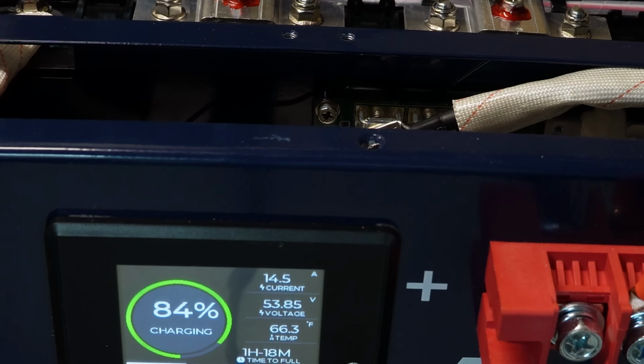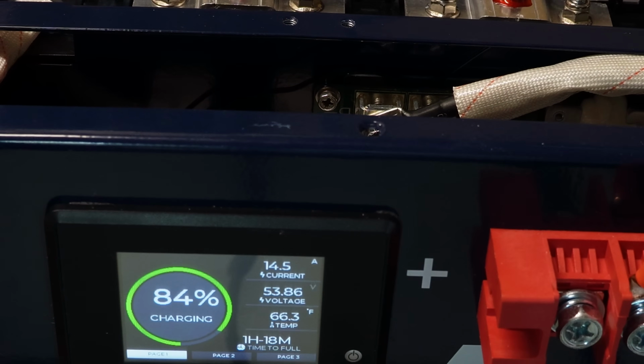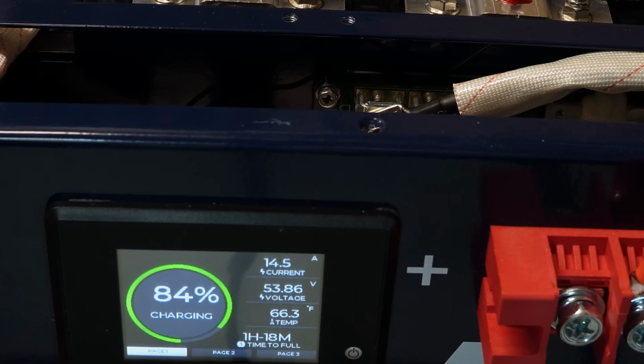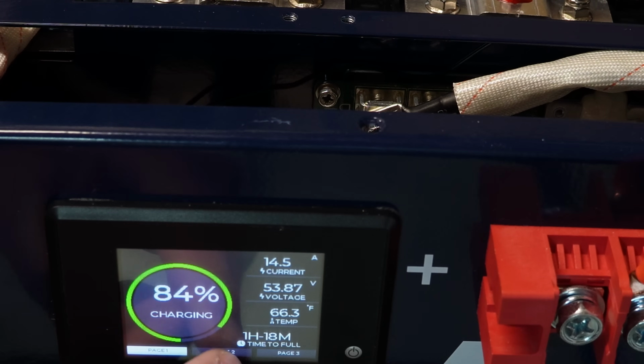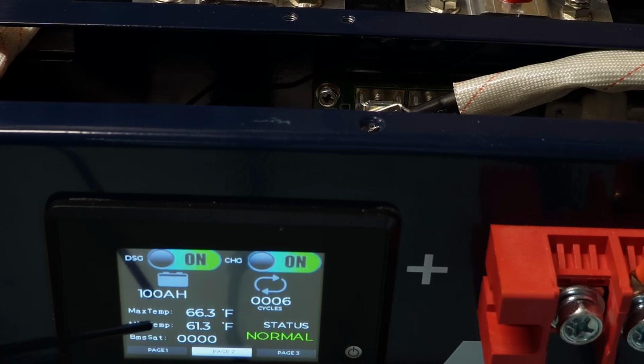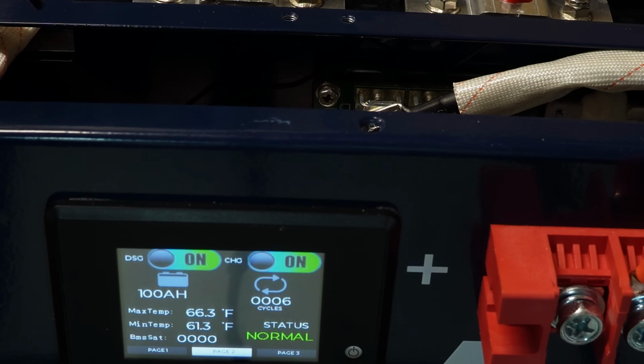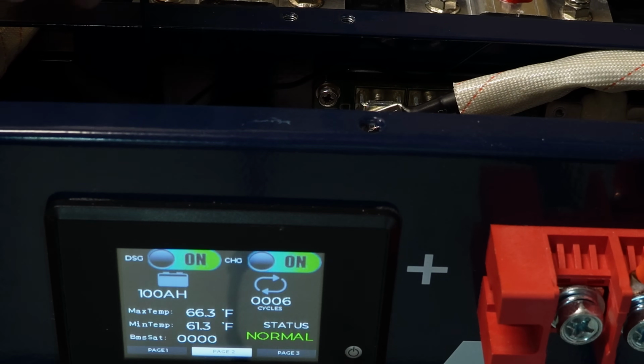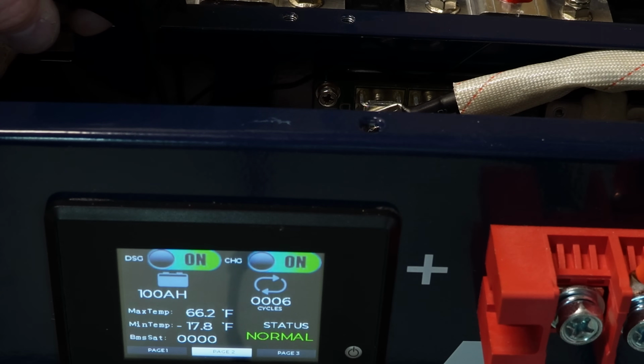Let me take a can of compressed air and see if I can sufficiently cool down that low temp sensor. And we're gonna watch over here on this display. Minimum temperature we're currently reading is 61.3. So we'll be able to see on that temperature sensor reading there what we're getting. So I'm gonna see what I can do to kind of force a low temp shutdown here. So if I can get this canister nozzle down in there. Yeah, and that's shut off immediately.